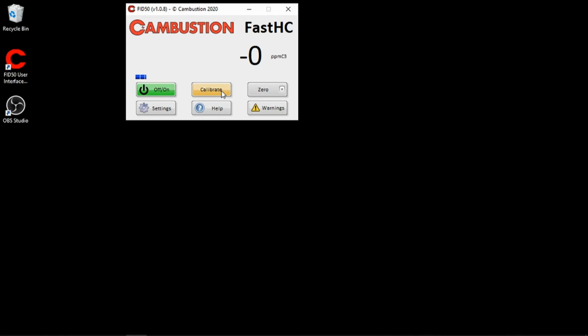If I now calibrate the instrument, if I press that calibration gas button, it now starts to flow zero gas, and it will look at any offsets on the system and dial out those offsets. It will then flow our calibration gas and will set the system output to match the calibration gas value. So it should settle at 1900 parts per million, and it will fix that as our cal gas value. Now that it's finished the calibration routine, the calibrate button has gone green and we're basically ready to sample. The span gas button reverts back to samples, so you're all ready to take some data.